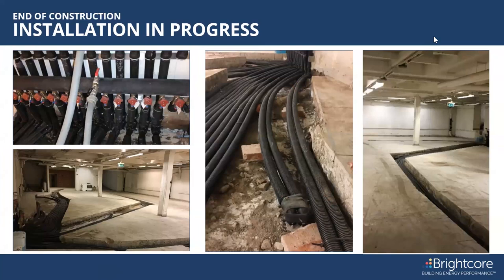We test every hole per IGSHPA standards, the International Ground Source Heat Pump Association. There are certifications involved with flushing and pressure testing, and even during construction we keep them pressurized so that if something affects the pressure, we can isolate and fix it easily. These systems are rated for 50 to 100 years of proper operation and maintenance.